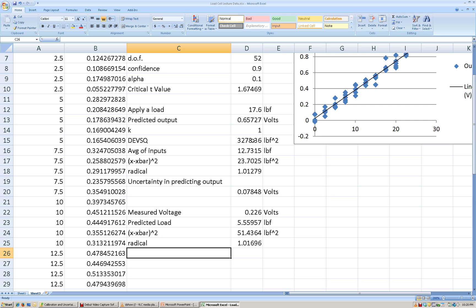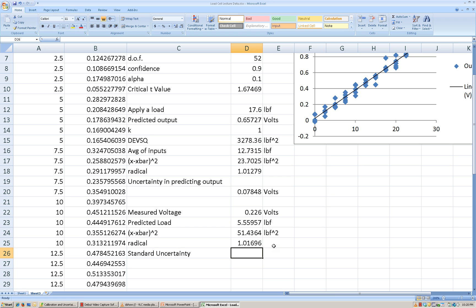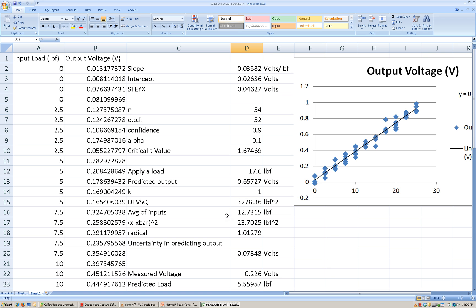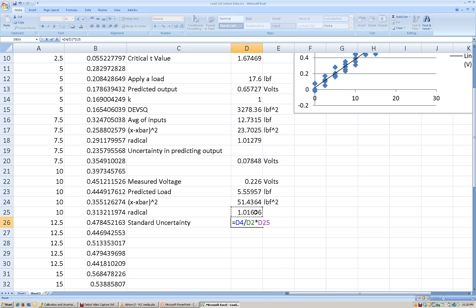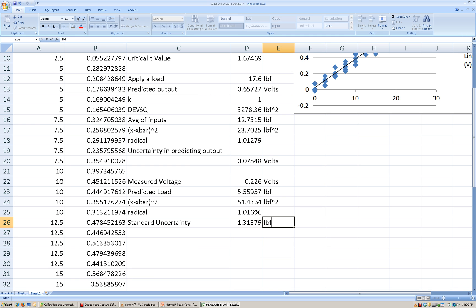This radical should be a unitless value. Then to come up with the standard uncertainty in predicting the load — the input value based on the output value — I take my standard uncertainty value, divide by the slope, and then multiply that by the radical term. This is the standard uncertainty in pounds-force for predicting the load based on the voltage measurement.